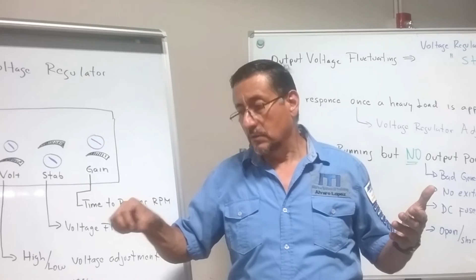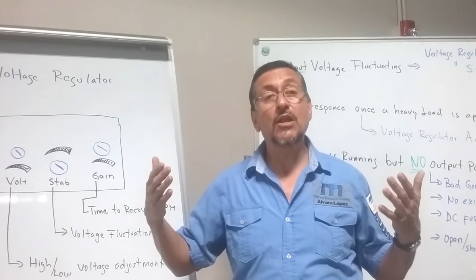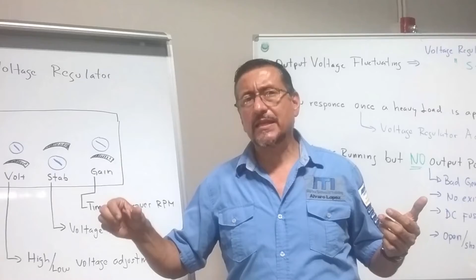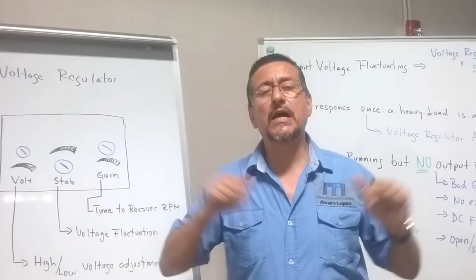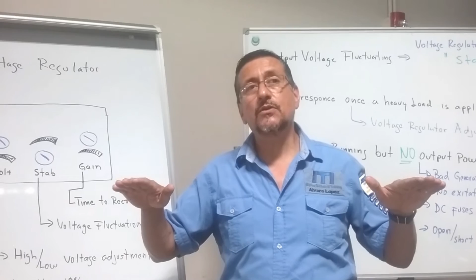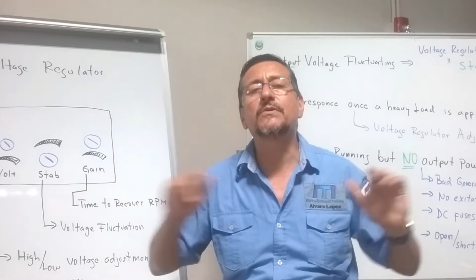Immediately you start to apply load, other load, and finally at the end you apply the heavy loads, air conditioning equipment or pumps. When you apply the heavy loads, you hear that the generator decreases the RPMs but immediately recovers the RPMs. In some cases, when you apply heavy loads, the generator decreases the RPMs and takes more time to recover the RPMs. In that case, you need to adjust with this pot, the gain.